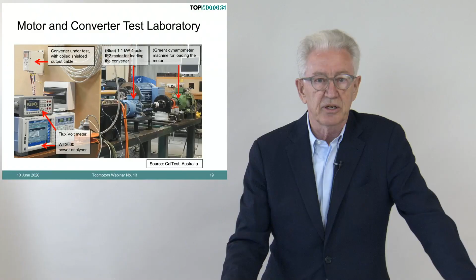Now, when you look at motor testing standards today, they're quite mature. There has been a long decision making process over the last 20 years, and for about 10 years, we can say we have an internationally agreed method to test motors with very, very good accuracy and very good repeatability. In the case of the converter standards, we are just starting. The first converter standard was published 3 years ago, and it had a description of testing which proved to be not so watertight. Therefore, we launched a new research program.